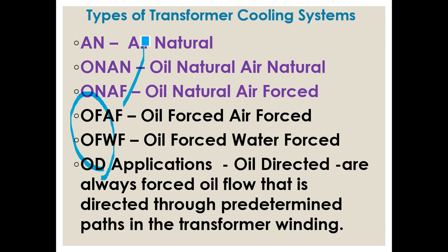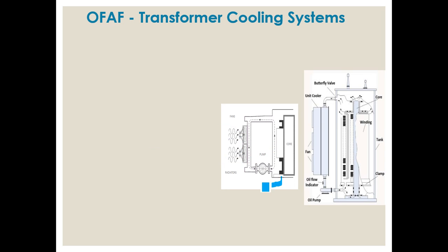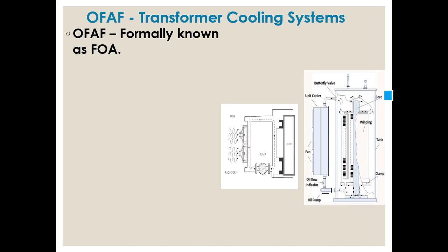In OFAF - oil force air force - the air is forced by a fan and the oil is forced by an oil pump. Inside the main tank you can see the oil getting circulated through the pump. The oil flows through this area, forced by the pump, while air is forced by the fan. OFAF is used for bigger capacity transformers.